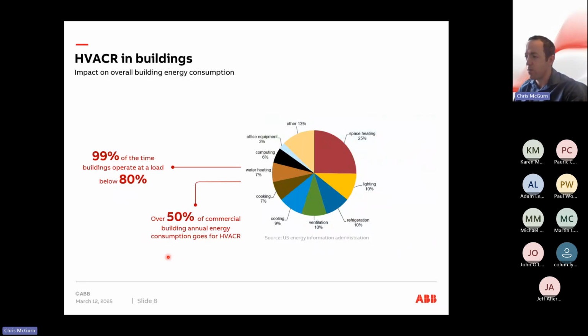So this is an interesting slide that was sent to us from the factory. It sort of shows a breakdown of how much commercial energy is actually used in the HVAC/R industry. So you'll see here over 50% of a commercial building's annual energy consumption goes into the HVAC/R, into heating, into ventilation, into refrigeration. And within that, 99% of the time, the buildings are actually operating at a load below 80%. So the machines themselves tend to be designed in a way where the efficiency is stated at 100% load. But that is very rarely the case. You very rarely have a motor, a machine, a fan running at 100% load all the time. In general, it's running below that load.